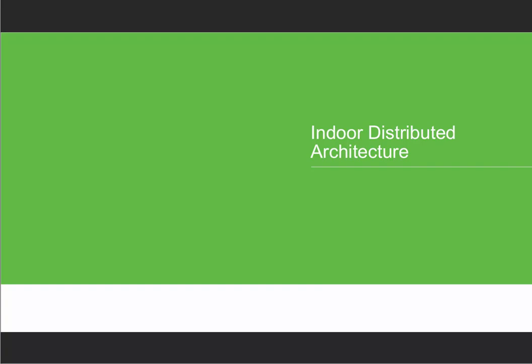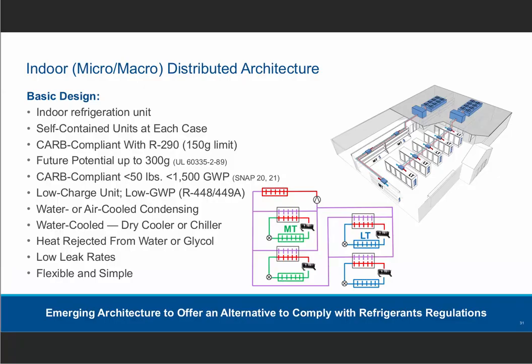Now jumping into the indoor distributed architecture, the basic design is that the refrigeration unit, basically the condensing unit, is mounted indoor. So either on top of display cases, using the display case as an example here, or on the bottom of supermarket islands or prep tables, that refrigeration unit is going to be indoor. It can be propane up to the charge limit allowed, or a refrigerant like A1, R448, R449 are two of the most common ones. Air-cooled is an option.